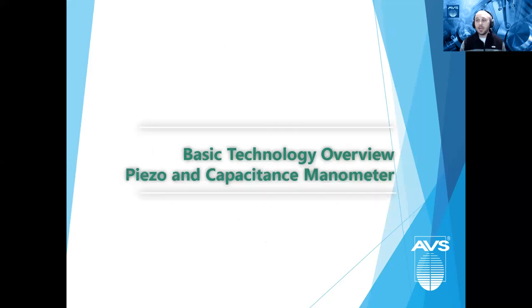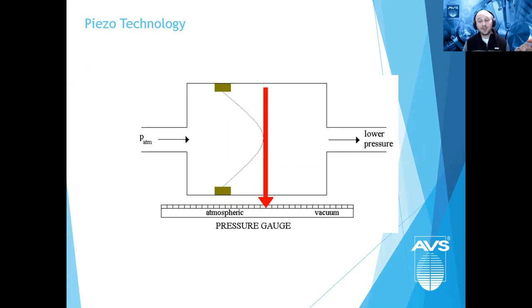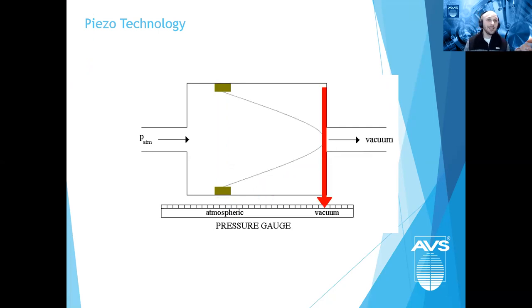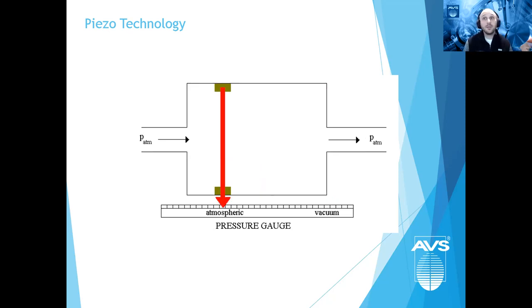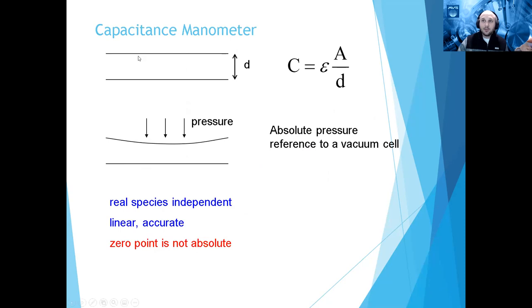Transitioning to piezos and capacitance manometers for the final section. Both work on the same basic principle: there's a diaphragm, and based on the force of the gas, the diaphragm moves. We measure the capacitance or displacement of that diaphragm to determine pressure — the more pressure, the more the diaphragm bends. This is an absolute, direct measurement. A capacitance manometer has a reference side held at 10⁻⁷ torr by a getter pump, which is lower than any capacitance manometer can measure, giving an extremely accurate and fast response to actual pressure regardless of gas composition.